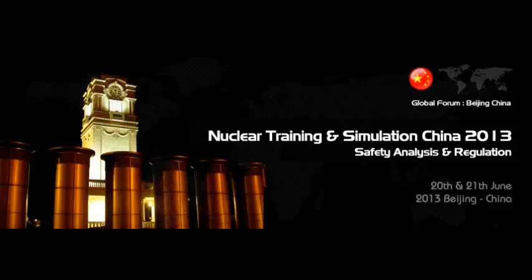From a simulator standards point of view, I really don't see much of a difference at all. There's a well-adopted minimal standard for nuclear power plant simulator design, which is the ANS 3.5 standard. So most people adopt that. Some request a higher fidelity solution, but that is the minimum. So all of the simulators being built around the world pretty much meet that standard by any of the vendors.